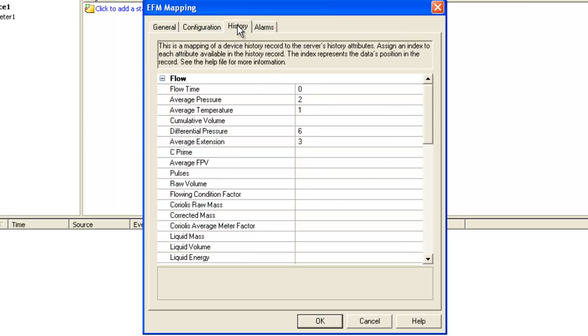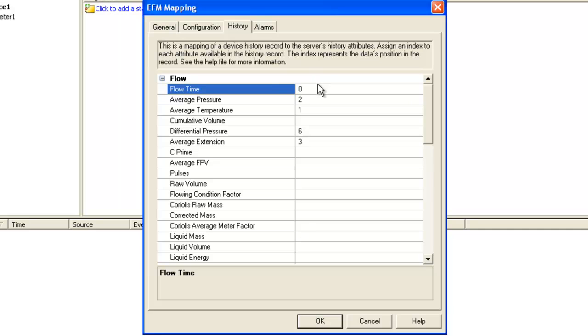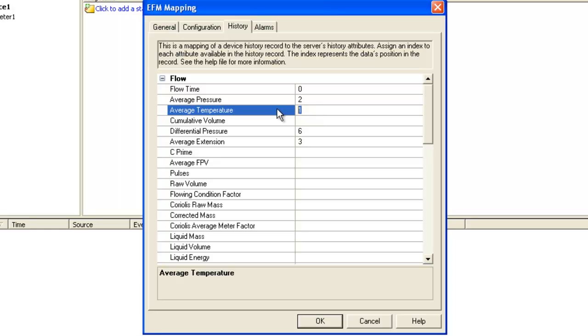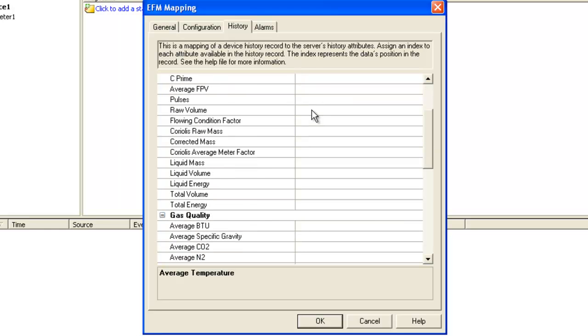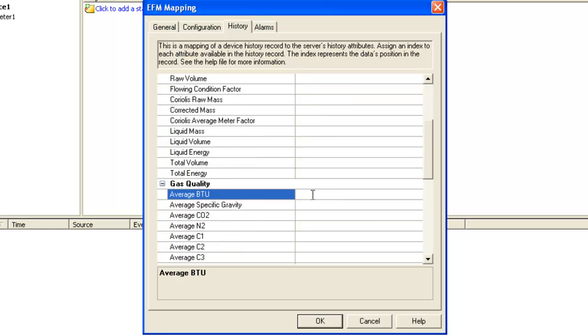History data is easier. It's basically just an array of floats that come back from the device, so we allow you to do a zero-based index into that array to assign floats to specific attributes. So flow time is the first element, average temperature is the second, so forth and so on. To leverage the gas chromatograph data, we would just use a Q syntax in front of the index.